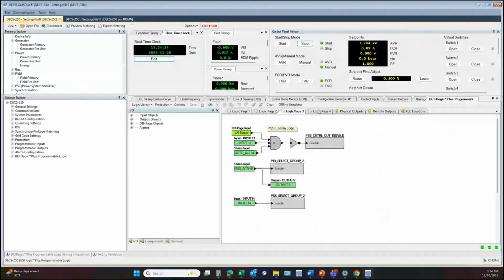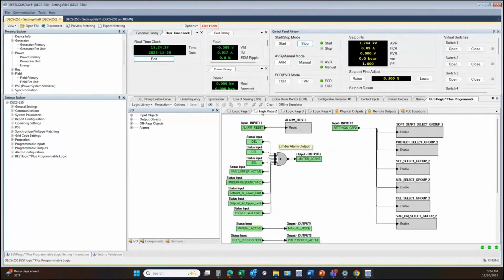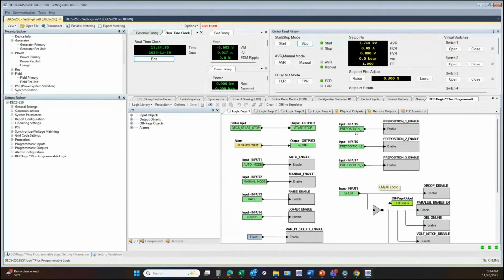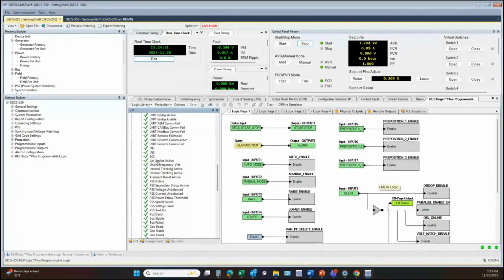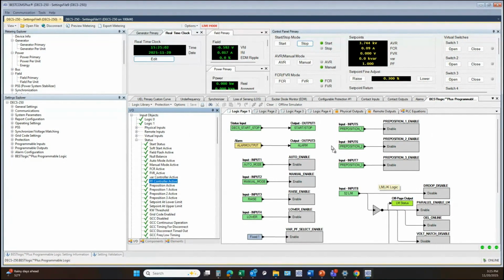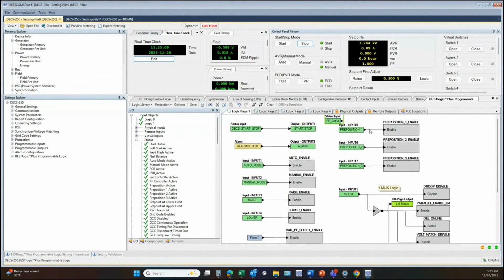And again, you have 4 logic pages. You can create whatever you choose on those logic pages. Prepositions is another area where we normally recommend setting up some logic. You would set up a preposition for example, if you do go into power factor control, you can go into this IO list, go to status, and see a long list of different status inputs. So power factor controller becomes active. I can drag that over and I can drop it somewhere on my logic page, and I can delete that line.